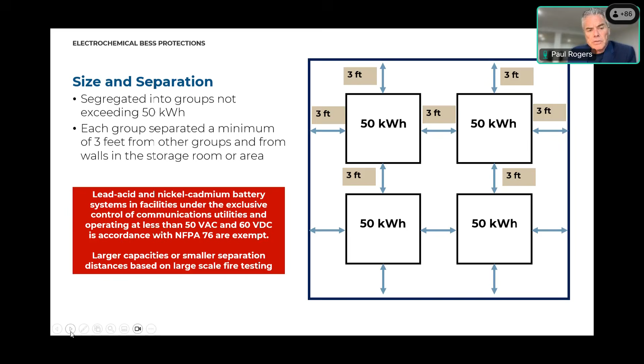Okay, the MAQs, the maximum allowable quantities, this is in a section that gets into the maximum allowable quantities. Can we go above these maximum allowable quantities? We sure can, we definitely can go above these numbers. As a matter of fact, if you take a look at most of the battery energy storage system cabinets already out there, they already exceed this number, already above and beyond these numbers.